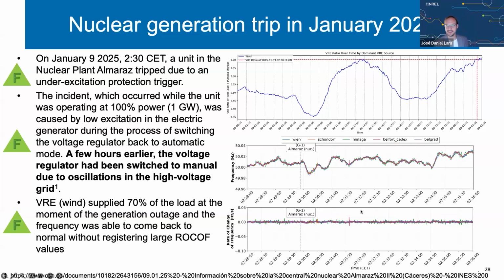And you can see here from the data that we collected for the frequency during that event that the frequency barely moved, that the rate of change of frequency barely changed. So again, it is not a matter of whether frequency alone and renewable energy penetration or inverter-based generation could be the culprit of a runaway of frequency, because the Spanish system has already operated and survived events with similar amounts of renewables and similar amounts of inverter-based generation in the system.